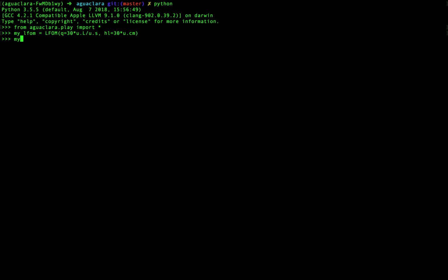So now if we inspect that, like you can do my LFOM dot n orifices per row, and you'll see there's 13, then 9, 5, 4, 4, 3, 2, 3, 3, 2, 3.